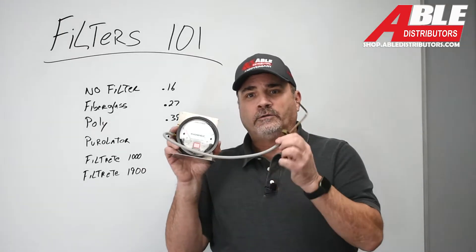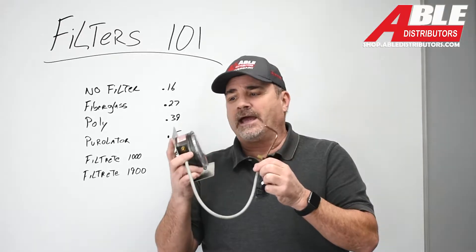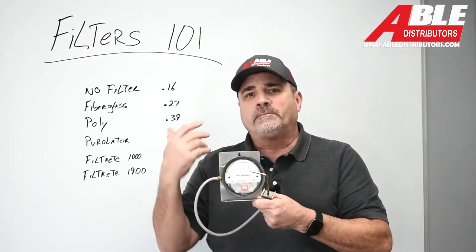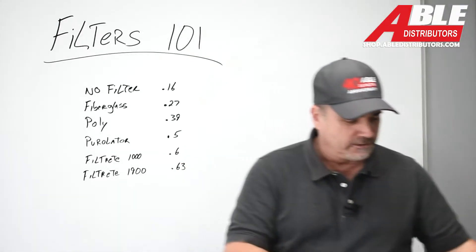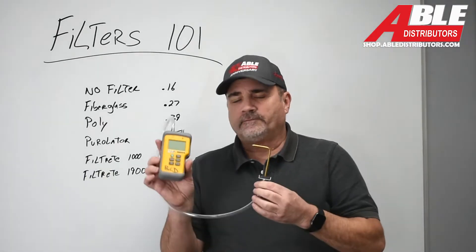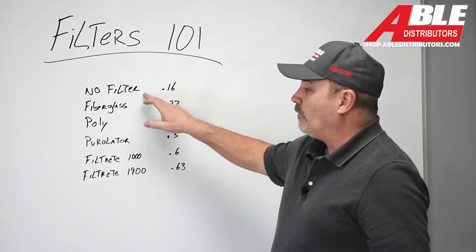I had two pieces of equipment all hooked up. I had an old Magnehelic on the right side of the furnace — this was for two reasons: it's super easy for me to read, and I wanted to see how close a Magnehelic is to a digital. So I also had the UEI 201B, which I like a lot. I had two measuring devices and started with no filter.